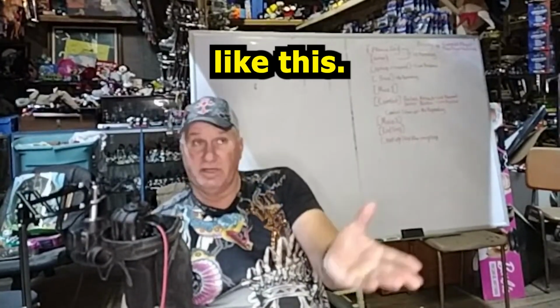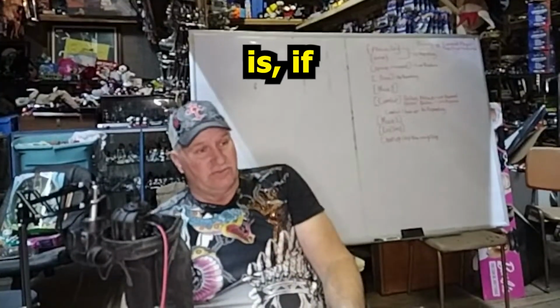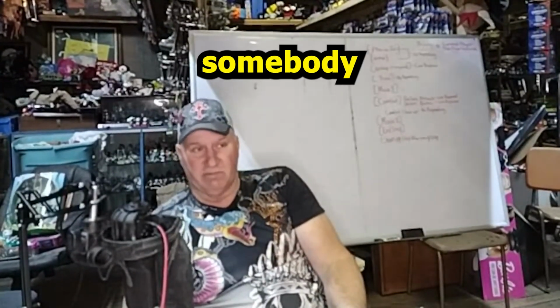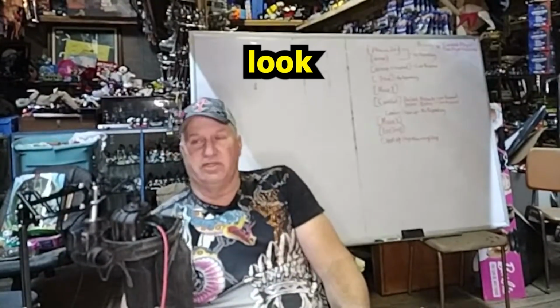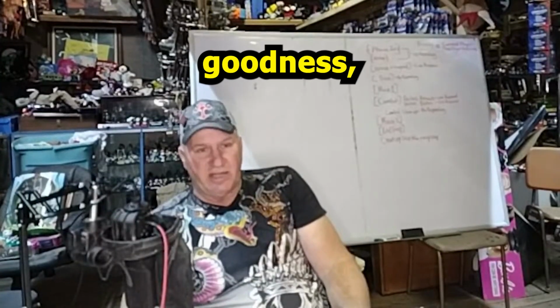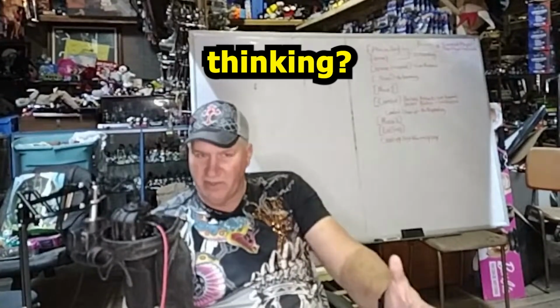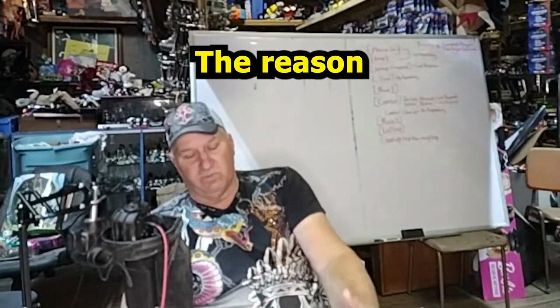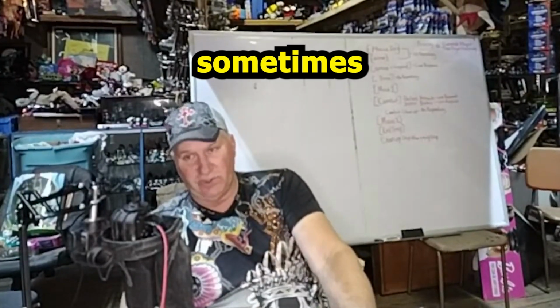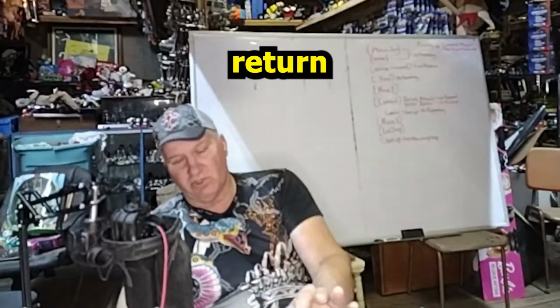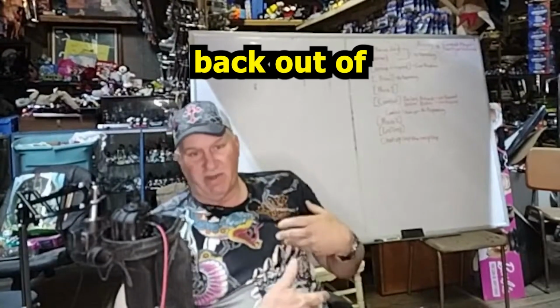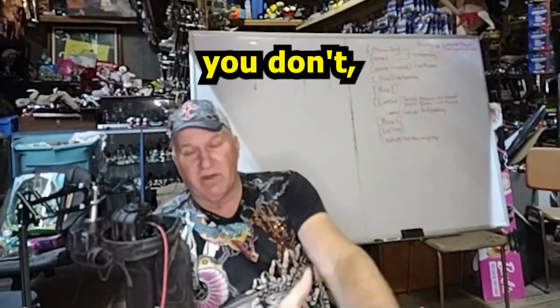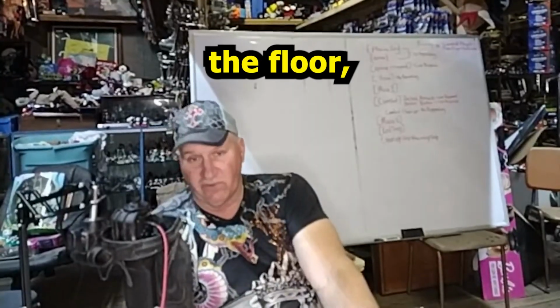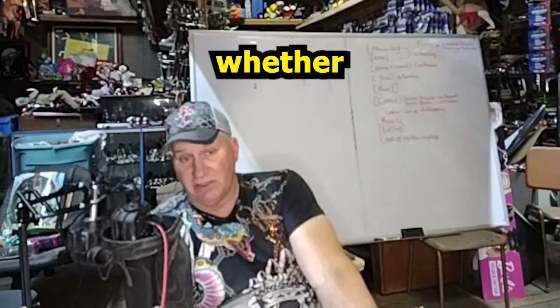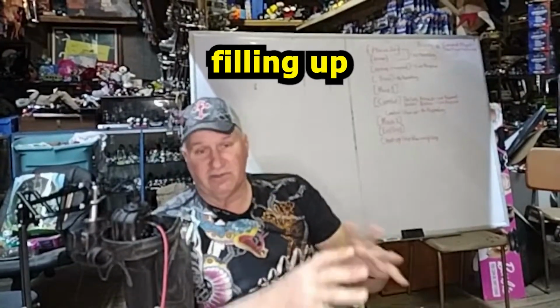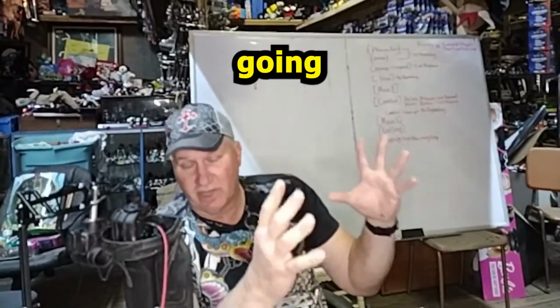Another thing to check: if you've installed, or had someone install, new doors. People often look at the old door and think, 'This is two inches off the ground, what were they thinking?' So they put in a new one that goes all the way down to the carpet. But that gap, and sometimes a vent in the door, exists because that's your return air path, pulling air back out of the room to recirculate and push more in. If the door goes all the way to the floor, it can't push any more air in, hot or cold, because there's no return. It's like trying to fill a balloon that's already solid, it won't take any more air.